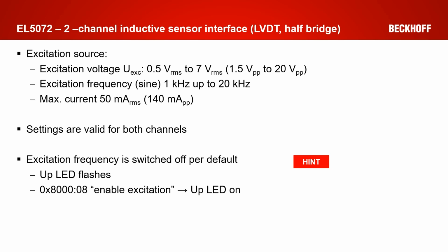The settings which are made in the CoE parameters for the first channel are also automatically applied to the second channel. One small hint from my side. The source is automatically switched off in the delivery state and must be switched on separately. The main idea behind this is that you will not accidentally feed the probe with a wrong voltage or too high frequencies. You will see that the source is off because the UP LED is flashing. If you activate the source, the UP LED will automatically be on.